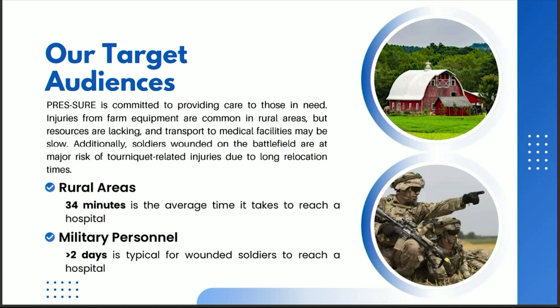Based on this problem and our identified target audience, we have designed Pressure, a reusable, rechargeable, semi-automatic pneumatic tourniquet that guarantees accurate pressure application and relief for up to 72 hours. Once the user places the device according to the printed instructions on the tourniquet, a single push of a button will inflate the tourniquet until blood flow has stopped. Then, 1 hour after application, the device will automatically begin 3-minute cycles of partial reperfusion, resetting to a 1-hour inflation after 5 cycles. By resuming the flow of blood at prescribed intervals, Pressure prevents extreme acidification of the blood and subsequently ischemic damage to remote organs and the injured limb. This significantly increases the safe tourniquet wear time.